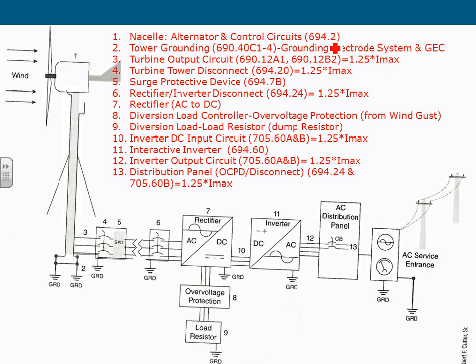If you disconnect it, right next to it is the SPD, surge protective device. You guys are very familiar with this one. We're very close to Mother Earth, so lightning is a big option here. What happens if you get hit by lightning here? You're going to burn some equipment. Worse than burning the equipment, that lightning surge is going to go right through your disconnect, right through your building, and burn the building wiring system too. It's not enough that you burned your tower, now you burn your wiring system.